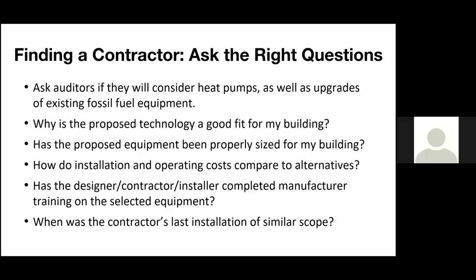We do not want to be oversizing our equipment whatsoever, because if you're oversizing your equipment, that means you're not getting the efficiency. That means you're going to have more of a short cycling process, and it's just not going to work out. So when you're going about a new project, make sure to get your design loads in, and make sure the proper calculations are done to size your equipment correctly.